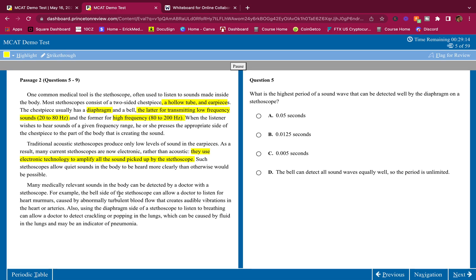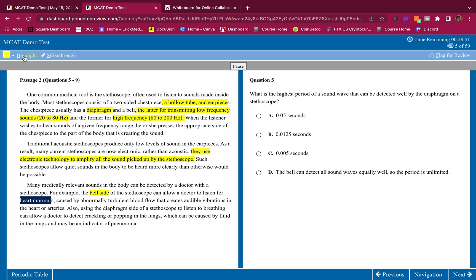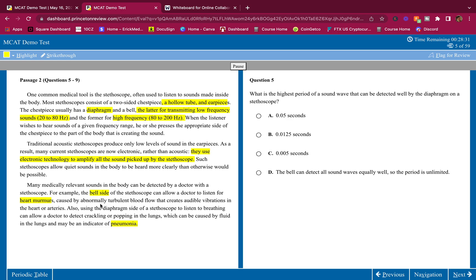Such stethoscopes allow quiet sounds in the body to be heard more clearly than otherwise would be possible. Many medically relevant sounds in the body can be detected by a doctor with a stethoscope. For example, the bell side of the stethoscope can allow a doctor to listen for heart murmurs caused by abnormally turbulent blood flow. I'm highlighting the bell side is for heart murmurs. And remember that the bell was for low frequency sounds. Also, using the diaphragm side of a stethoscope to listen to breathing can allow a doctor to detect crackling or popping in the lungs, which can be caused by fluid in the lungs and maybe an indicator of pneumonia. So the diaphragm, which is the higher frequency, can detect crackling in the lungs.